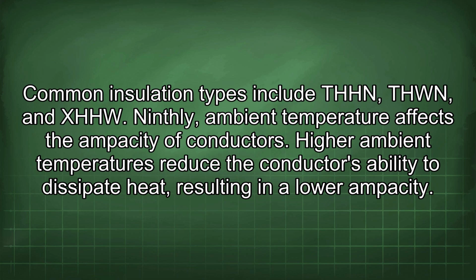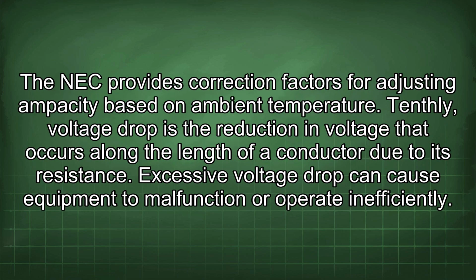Ninthly, ambient temperature affects the ampacity of conductors. Higher ambient temperatures reduce the conductor's ability to dissipate heat, resulting in a lower ampacity. The NEC provides correction factors for adjusting ampacity based on ambient temperature.